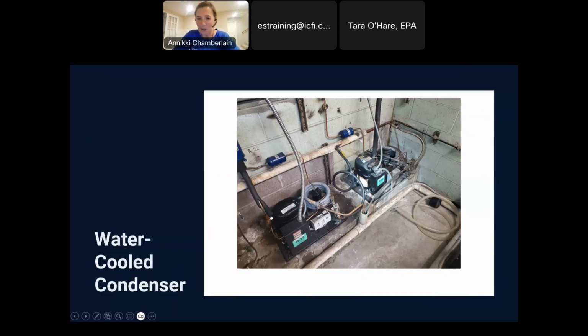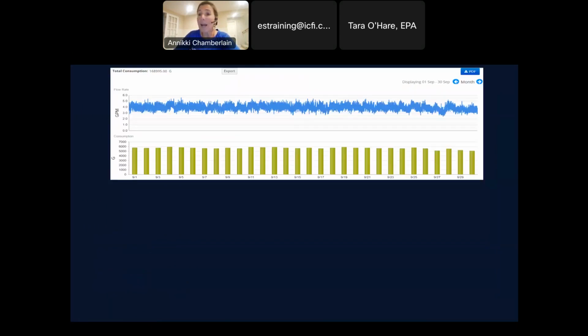There are a bunch of troubleshooting ways you can see that without metering it. We won't get into that today. But I know right now I have failed valves, and I've been there, so I know that all 5 of the valves have just failed. It means it's just running all the time. So not only do I know that I have a mechanical problem, but now I have the information that I need for a payback, because these things cost almost 6,000 gallons of water a day.